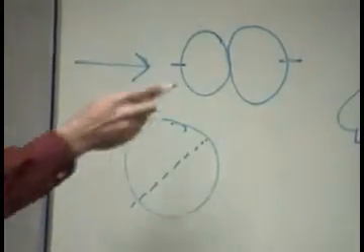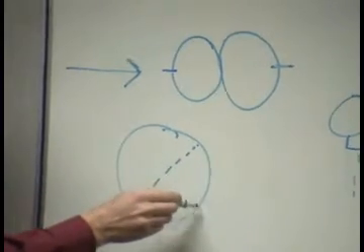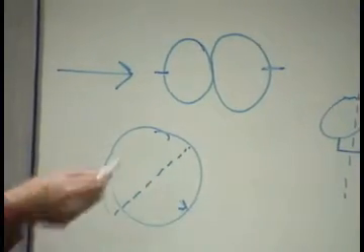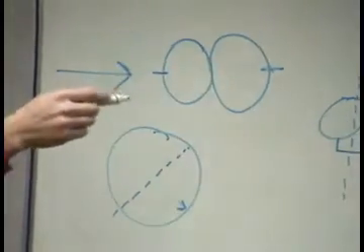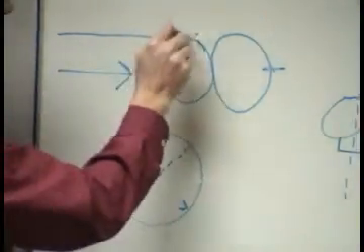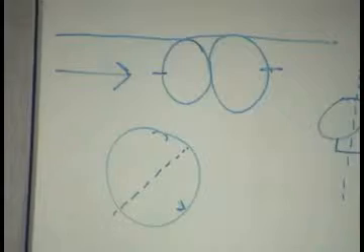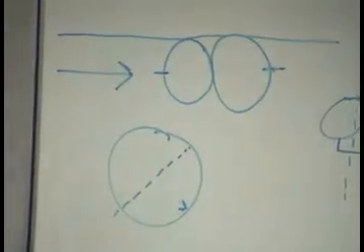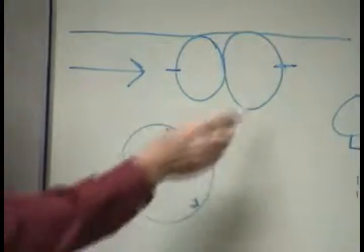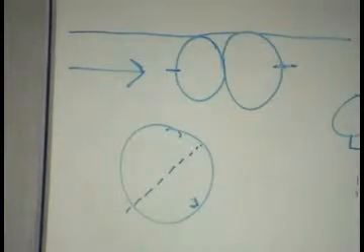And instead of reading static, or the pressure against the side of the duct, what they're reading is this downstream pressure. So your air's flowing along here, it goes along here, and this kind of creates a little vortex, a little low pressure area. So instead of the normal static pressure, you get something a little bit less because you're getting a little vortex off of that. So with our box, they call it the K factor. Our K factor is not 4005 like you're using. Ours is something else.